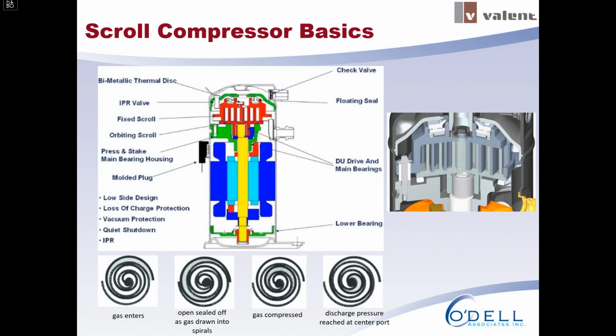So every once in a while, depending on the signals it receives, it'll unload, and it will reduce its capacity a little bit, and so that's how it modulates. An inverter scroll modulates a little bit differently. Instead of unloading, like that video is showing, there's no unloading, and instead it modulates the frequency of that scrolling motion. So if this were an inverter scroll compressor, it would show that green scroll changing speeds to modulate.